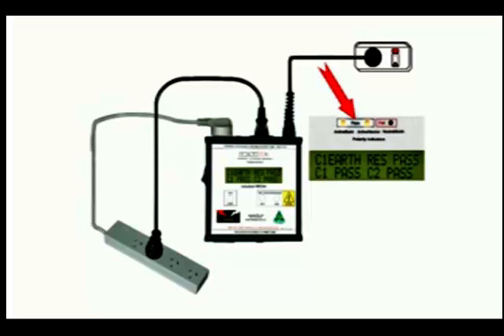The lights indicate that the polarity is correct. If the wiring was wrong, the fail light would show up. The top line of the display tells us that the earth resistance is less than 1 ohm, so we have a Class 1 earth resistance pass. And although an extension lead is an earthed device, the standard requires the more stringent leakage current test at Class 2 level, which is less than 1 milliamp, and that passes.